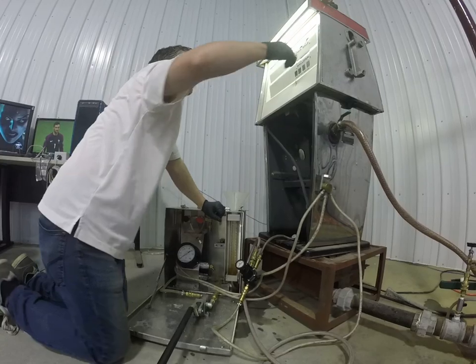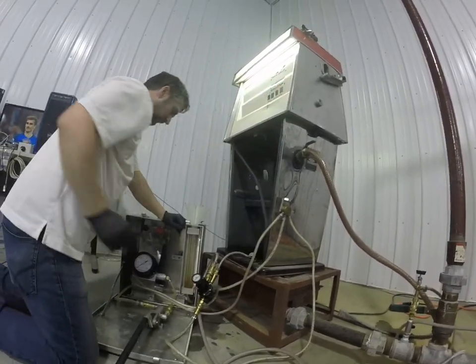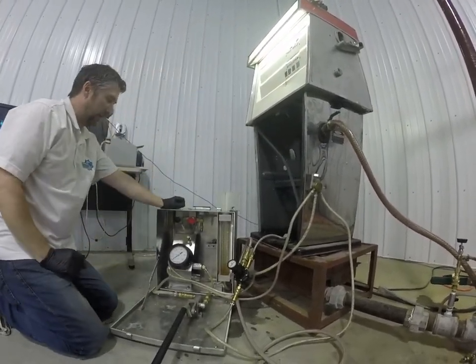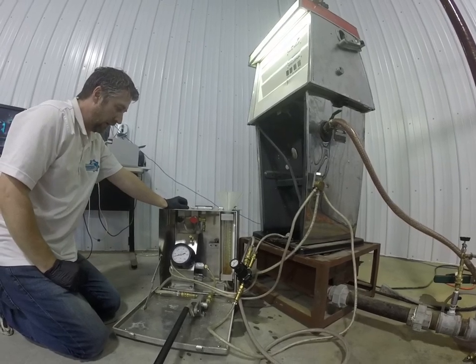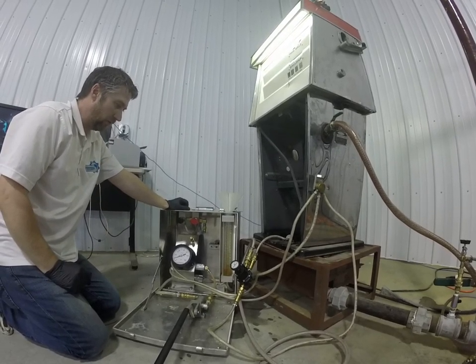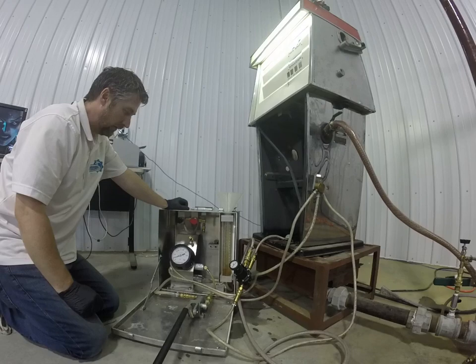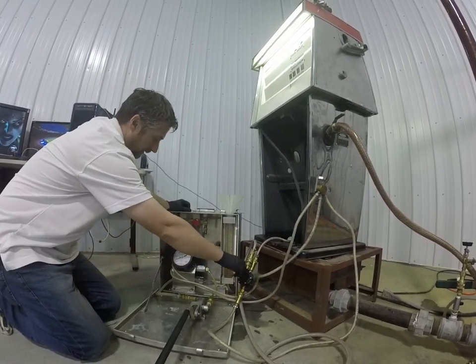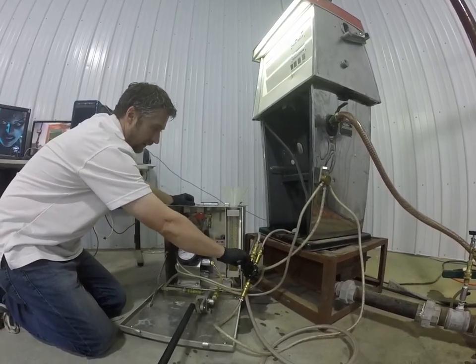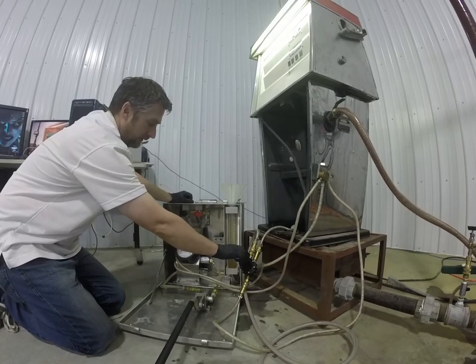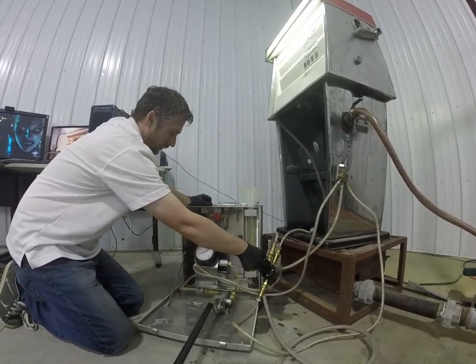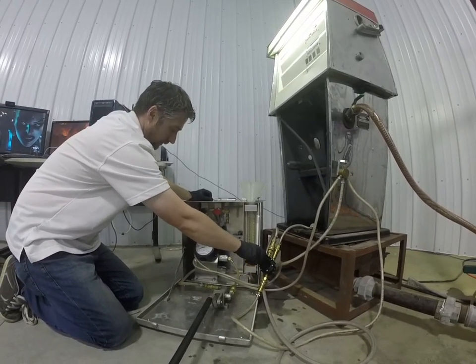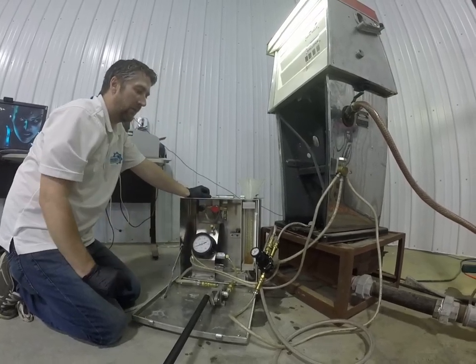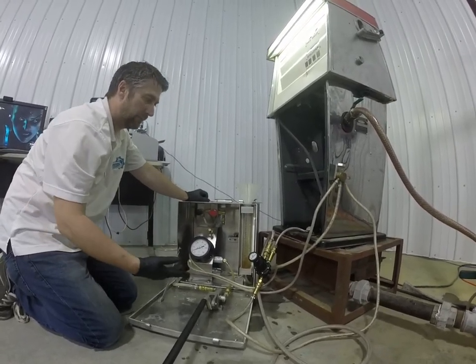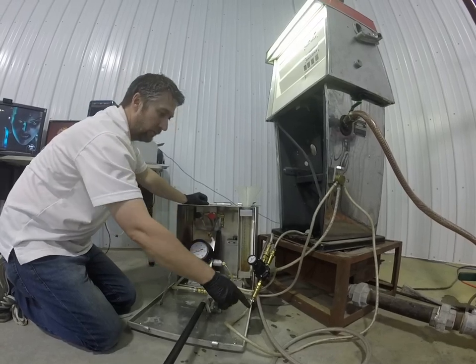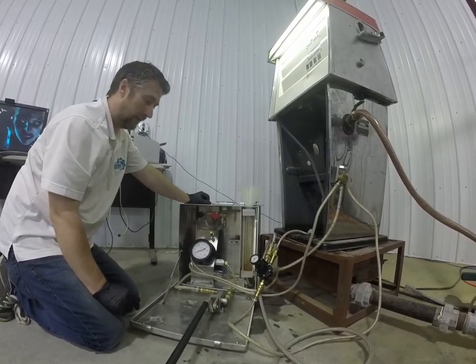We're going to start the dispenser, which will kick the pump on, and then the pump is going to be controlling the regulator to 10 psi. We can adjust the pressure if necessary with the regulator by turning it counterclockwise to reduce the pressure, or clockwise to increase the pressure. The reason we have the drain hose on there is that if there's an excess in pressure in the system, this will drain off safely to an approved safety can.